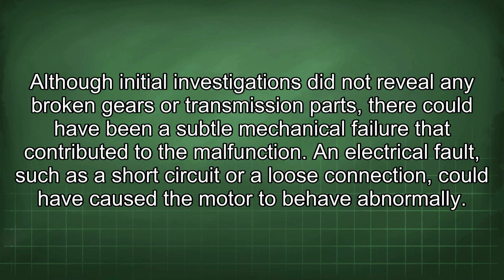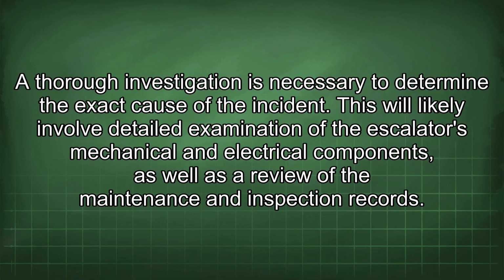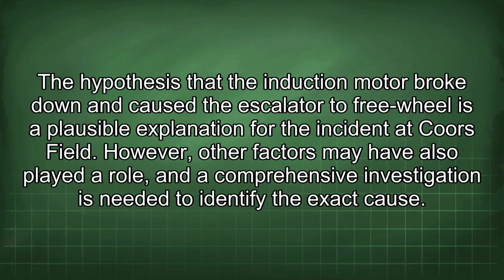An electrical fault, such as a short circuit or a loose connection, could have caused the motor to behave abnormally. A thorough investigation is necessary to determine the exact cause of the incident. This will likely involve detailed examination of the escalator's mechanical and electrical components, as well as a review of the maintenance and inspection records. The hypothesis that the induction motor broke down and caused the escalator to freewheel is a plausible explanation for the incident at Coors Field. However, other factors may have also played a role, and a comprehensive investigation is needed to identify the exact cause.